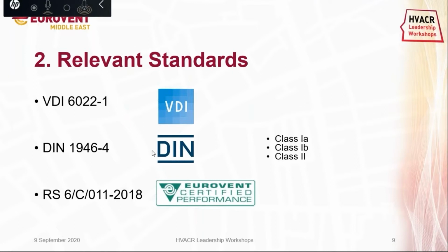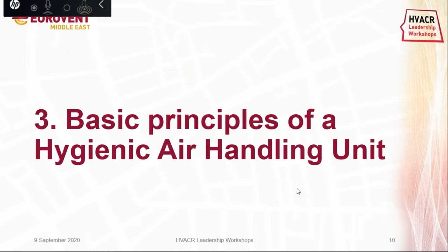It classifies the rooms in two classes, class 1, with 1A and 1B being for the surgery rooms, and class 2 is for the rest of the hospital areas. And then the rating standard from Eurovent, the RS 6/C/11 2018, which is also getting more and more attention every day, describes 3 levels of hygiene. Third one being the highest requirements, recommended for the food processes, pharmaceutical and clean rooms and equivalent. Level 2 is for hospitals, and level 1 is recommended for schools, offices, and hotels.